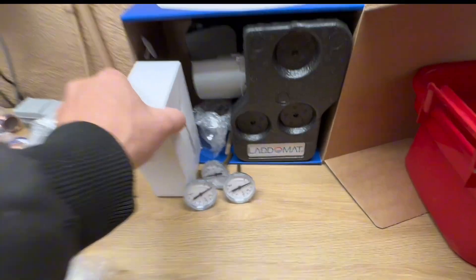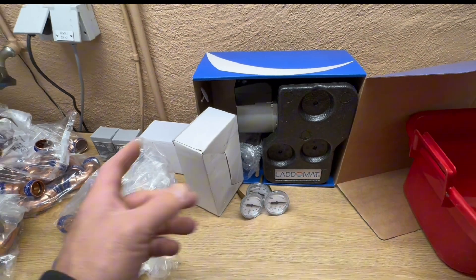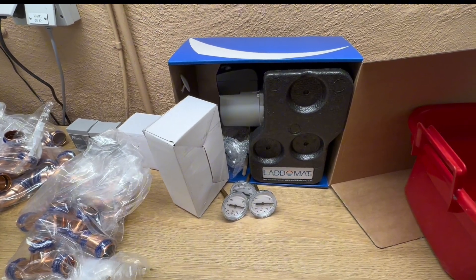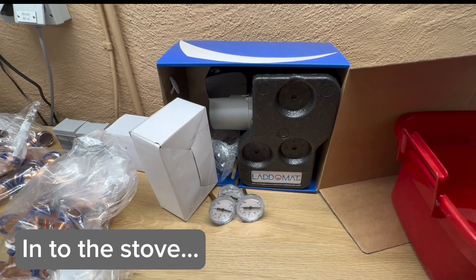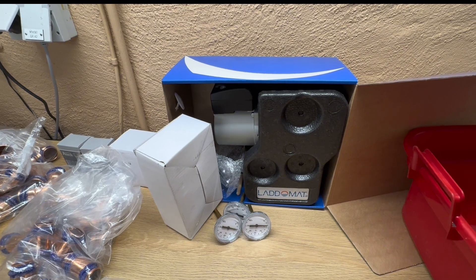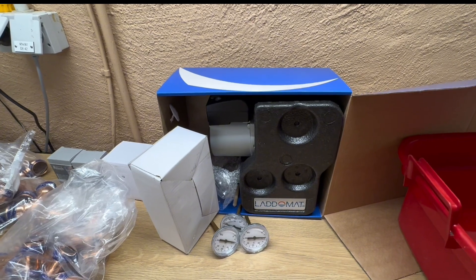Then we have this Laddomat here. What this does is sense when I am starting my fire stove, and it will then start to circulate the water inside the stove. When the temperature is right, it will start to push out the hot water to the tank. It will also make sure it never sends cold water into the tank — it always mixes the intake water with some heated water so we have an even temperature in the stove and avoid moisture and corrosion in the bottom of the stove.